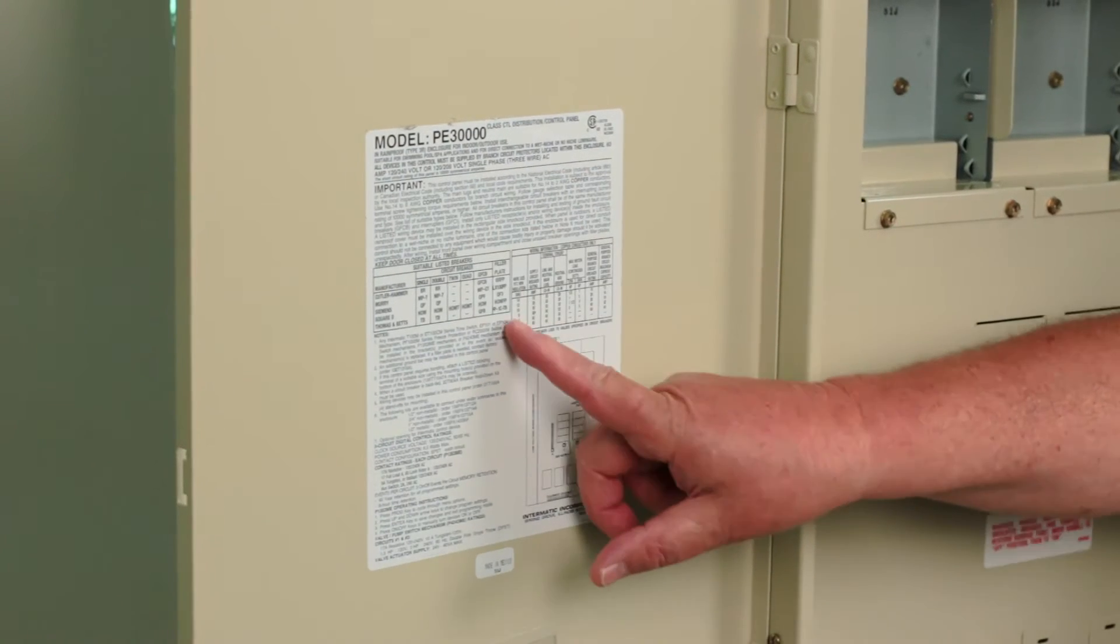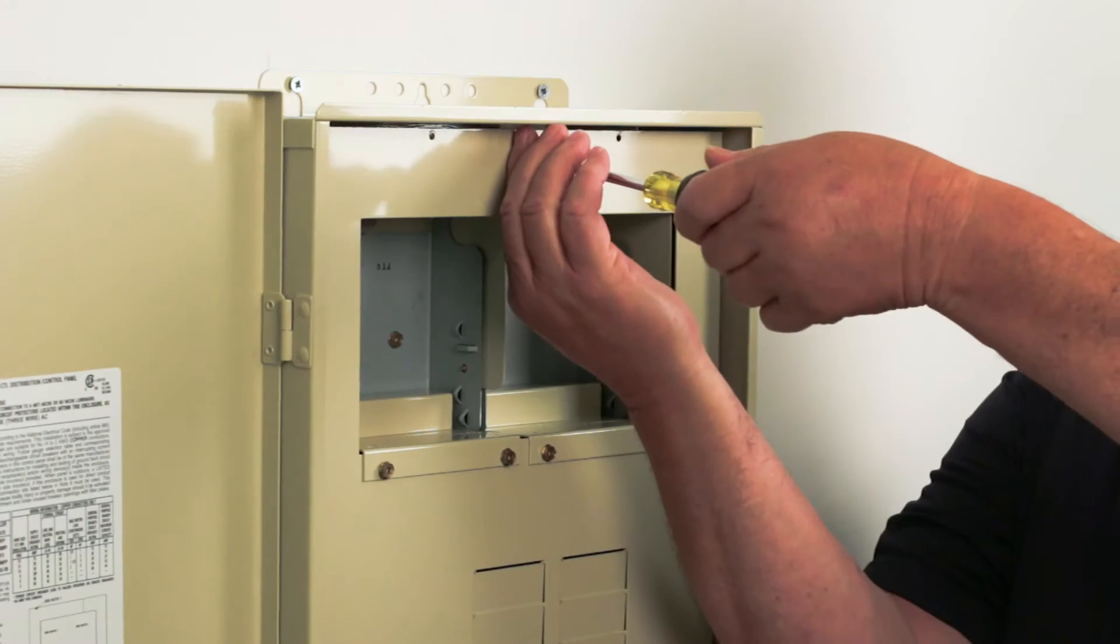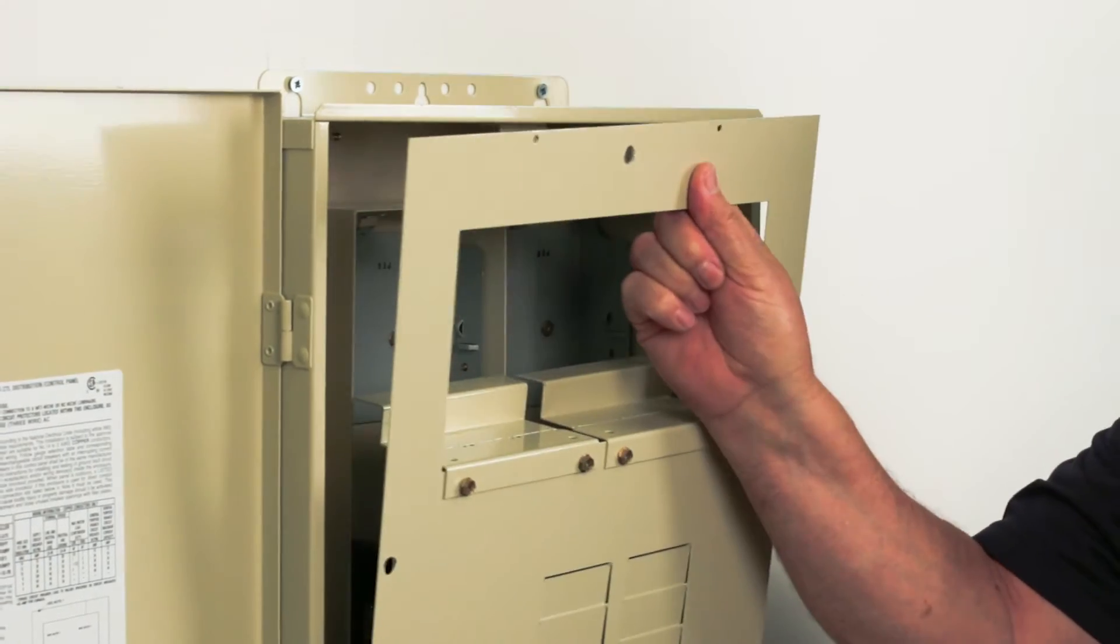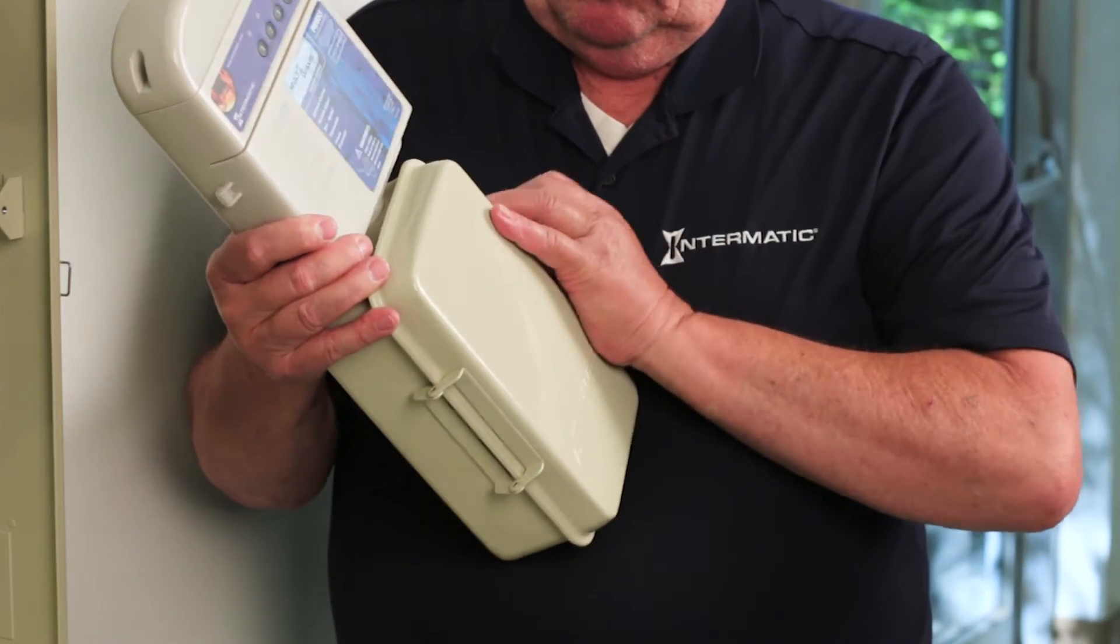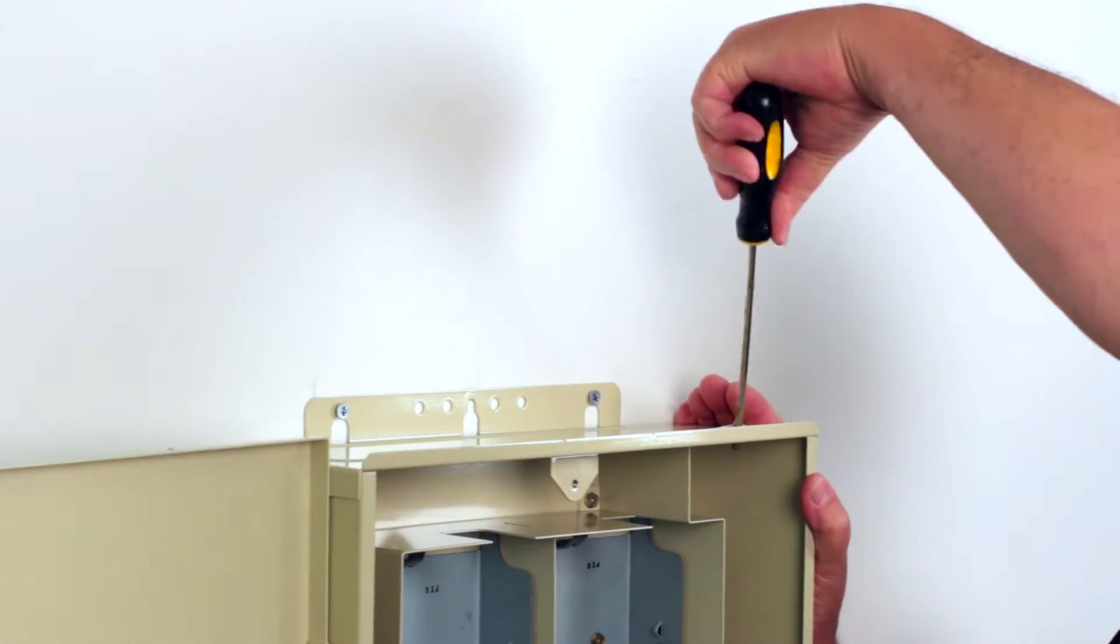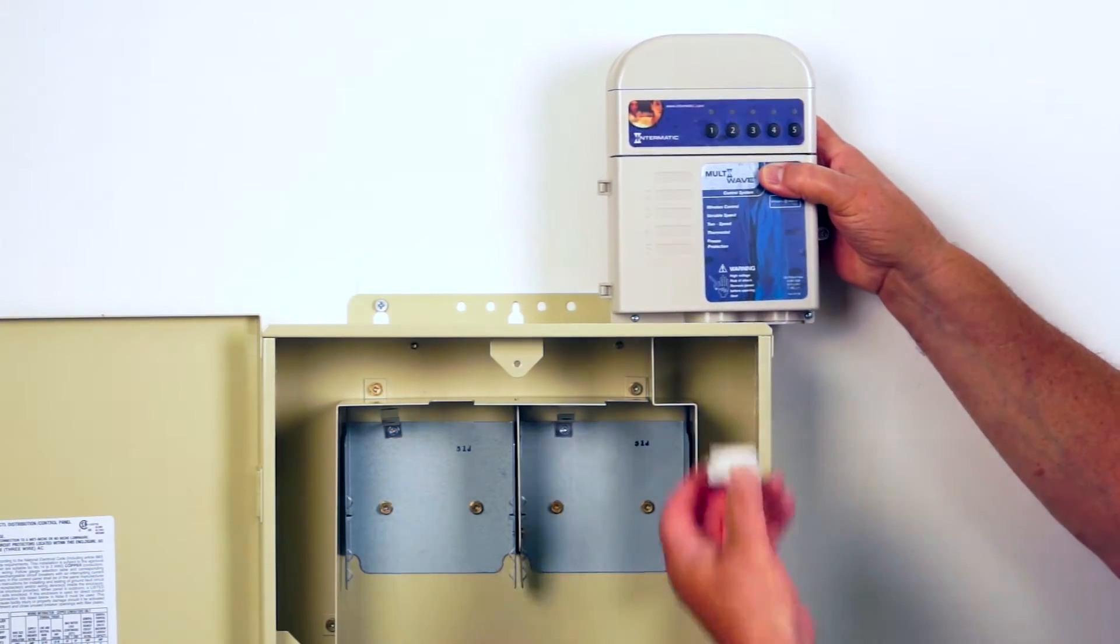Breakers are sold separately, so check the inside front panel for a list of acceptable types. Remove the dead front on the panel to install the MultiWave receiver. The receiver comes shipped attached to a small enclosure box. Unscrew the nut and gasket to remove the receiver. Mount the receiver to the top right knockout using the nut and gasket to keep the unit rain tight.